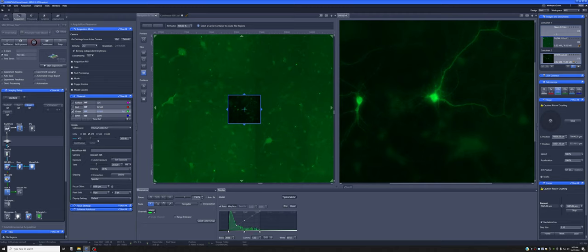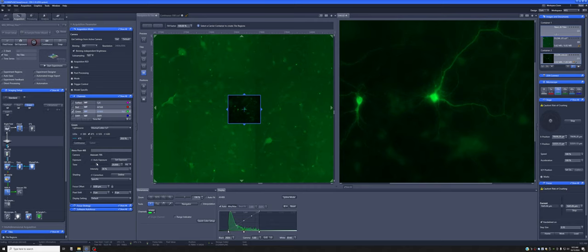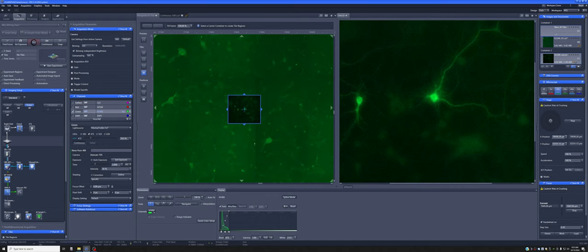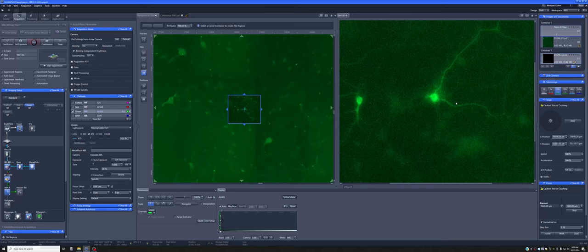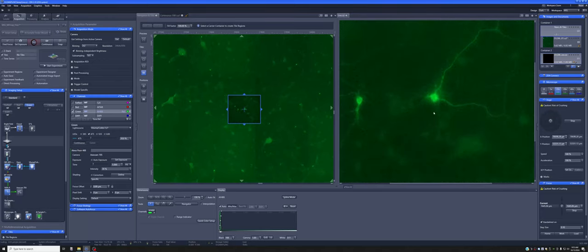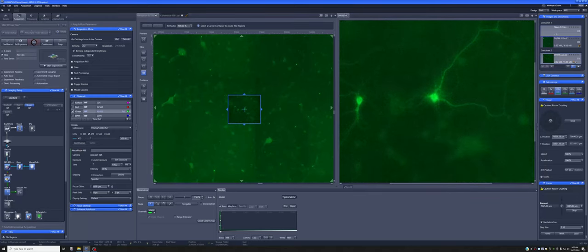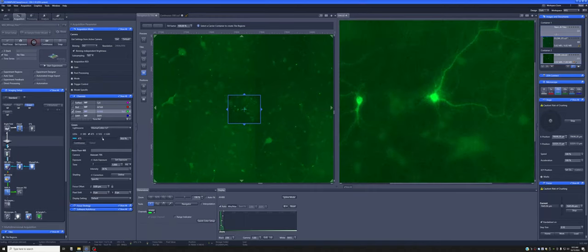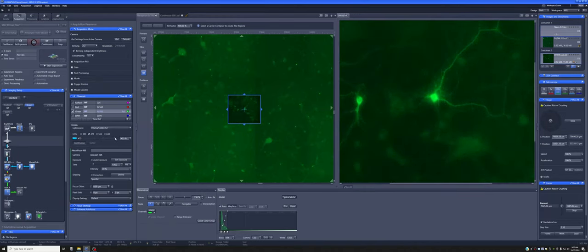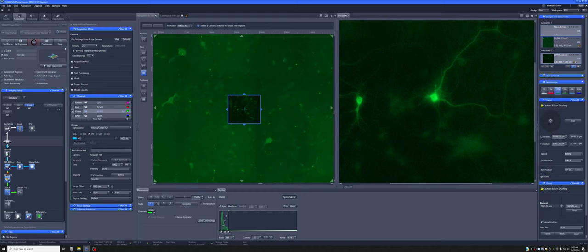And you have two things that you can adjust here, the LED power and the exposure. So if you reduce the exposure, it will go faster. But the quality of the image will be lower. We can go down to as low as a millisecond and it'll look quite poor. And we can compensate if we want by increasing the LED intensity. So we could do something like this to get a fairly good image with minimal exposure.